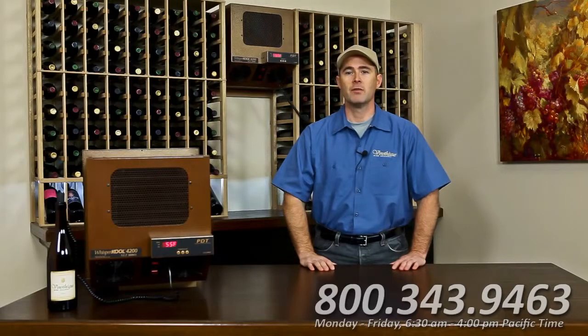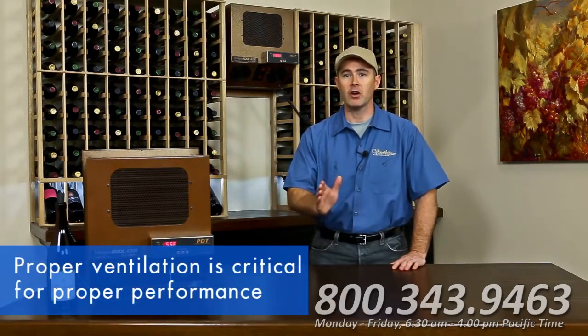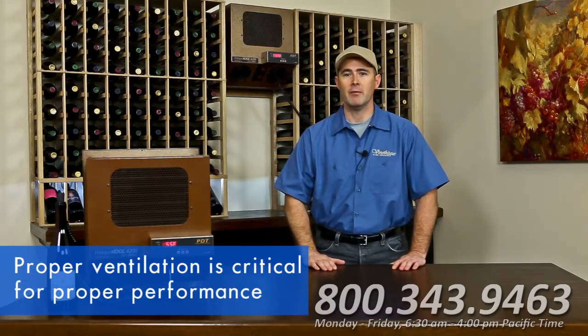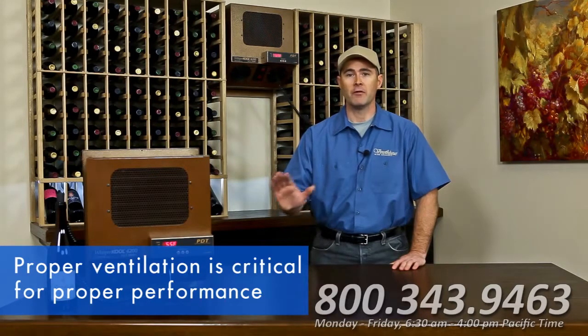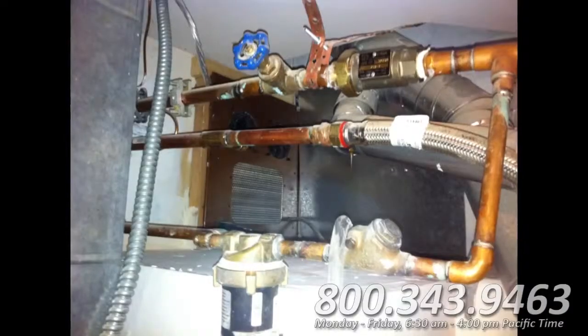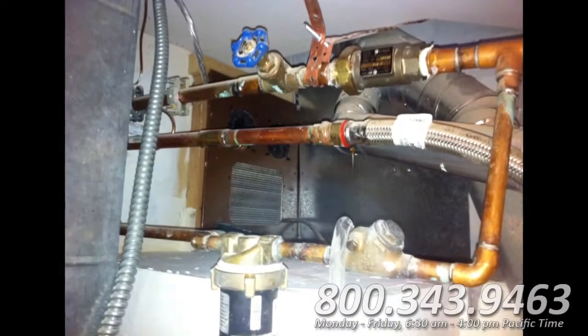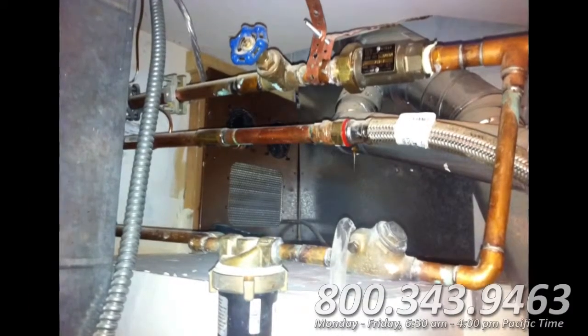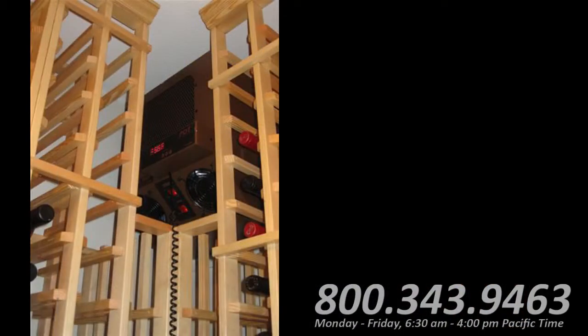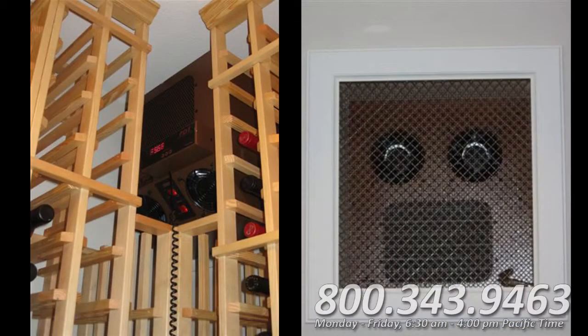First, let me say a few words about ventilation, because unobstructed airflow to and from the unit is critical to the cooling unit's performance, and most cooling unit problems begin with poor ventilation. The unit must vent to a large open area both in front and behind for proper air circulation. Don't run any pipes or ducting behind the unit once it is installed. Also, don't try to camouflage the unit by building racking in front of it or by attaching a decorative grill to the exhaust side, as this will obstruct the airflow.